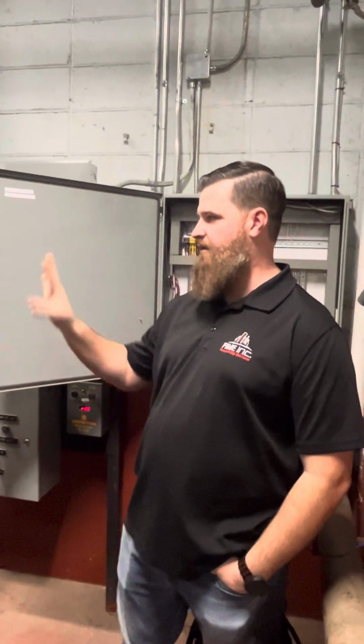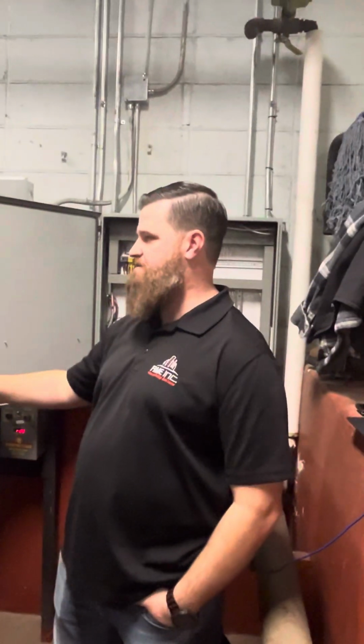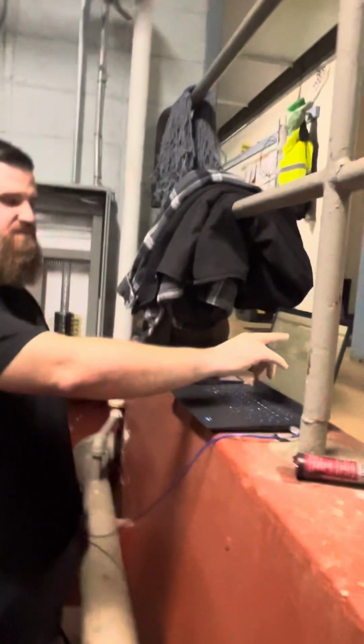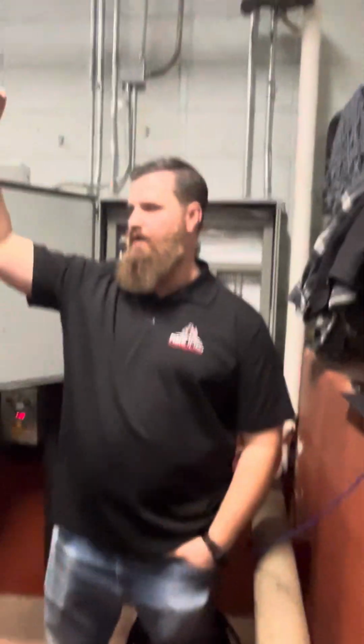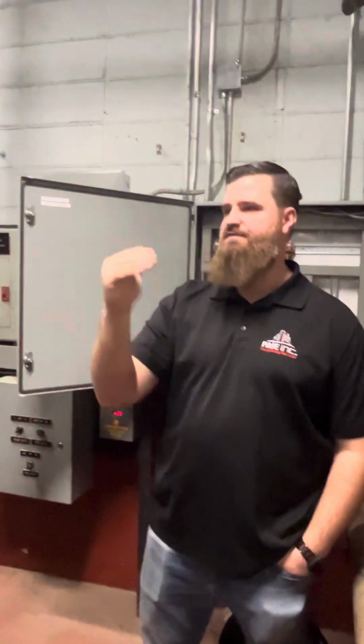Yes. By 3 pounds, does that mean all 3 boilers will run? Let me lower stop right there. I'm going to explain everything, how this all stages. It'll answer all your questions. Okay. So 3 pound set point. That's what we want at the pressure on the header. That sensor is sitting right up there. Okay. Now, 3 pounds is where we want to be roughly, but there's a differential on how we have to operate the boilers. So you're going to see us go below 3. You're going to see us go above 3, but the average is supposed to be around 3.